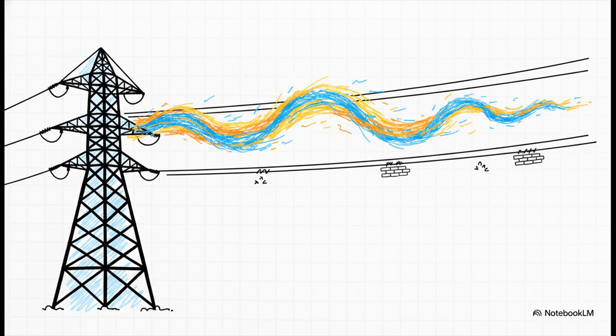This creates a specific, super important point called surge impedance loading, or SIL. Basically, if you load a line at exactly its SIL, the reactive power produced by the capacitance perfectly cancels the reactive power consumed by the inductance. The result? The voltage stays completely flat end to end. If you load it below SIL, the voltage actually rises toward the far end. Load it above, and it sags. That's why planning engineers treat lines as voltage limited below SIL and thermally limited above it.